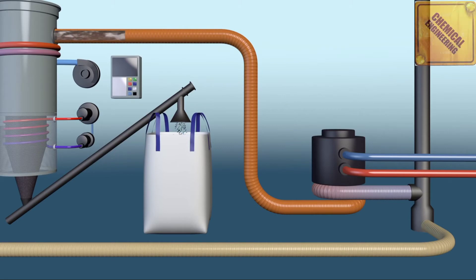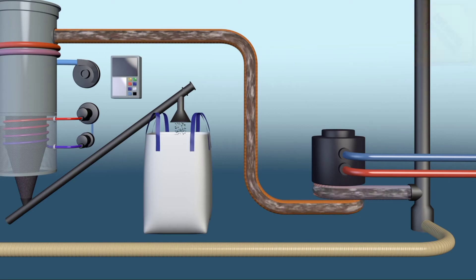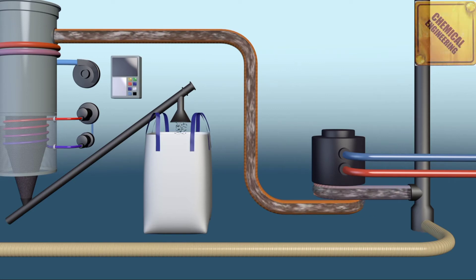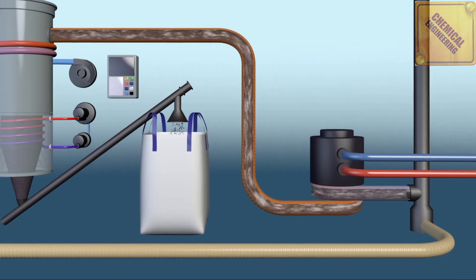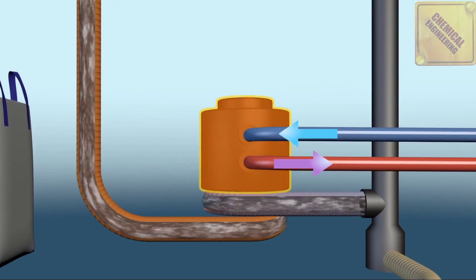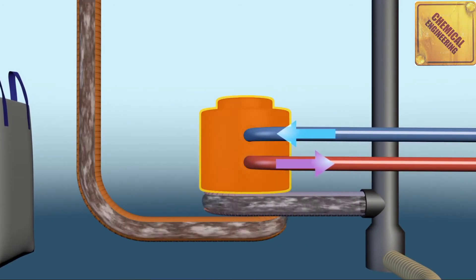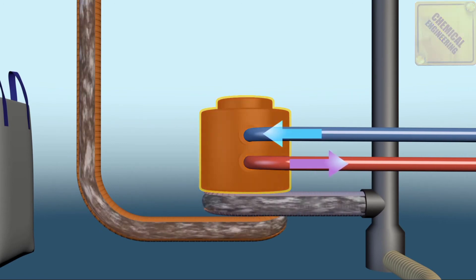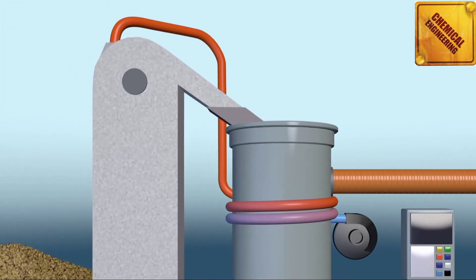Heat generation: the flammable gas has a relatively low calorific value, so the best way to make use of it is by conversion to hot water. Pyrolysis systems with productivity from 300 to 1000 kilograms per hour can supply district heating networks with a maximum capacity from one to three megawatts respectively. The yield of flammable gases depends on the type and quality of the processed biomass and the expected characteristics of the carbonized biomass.